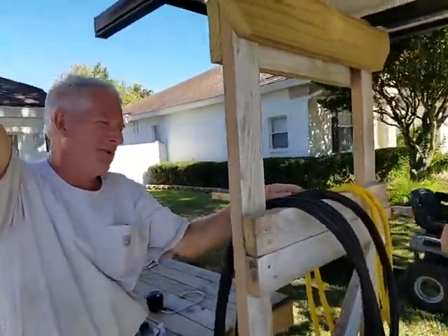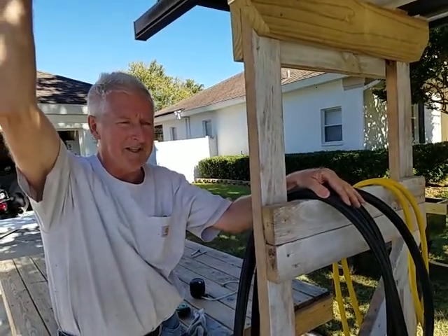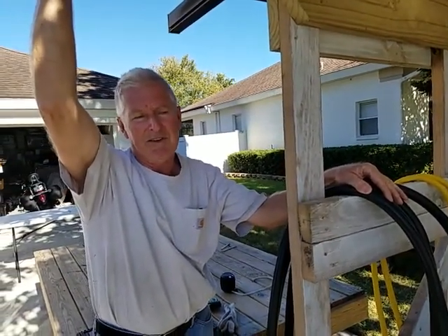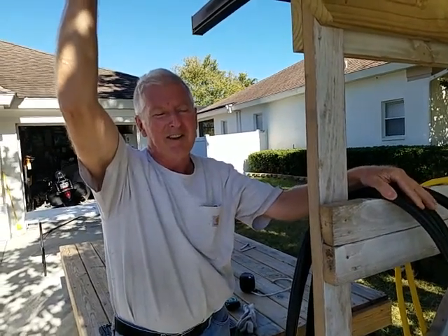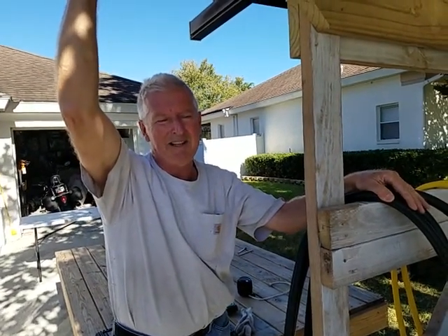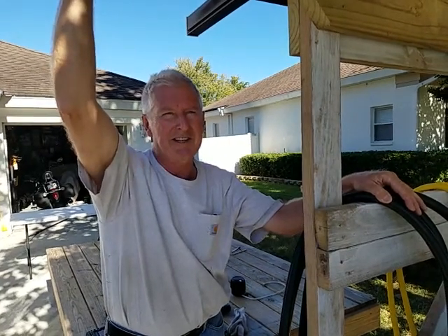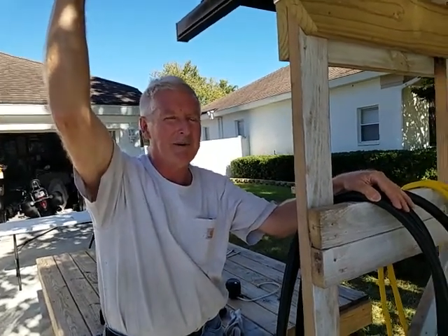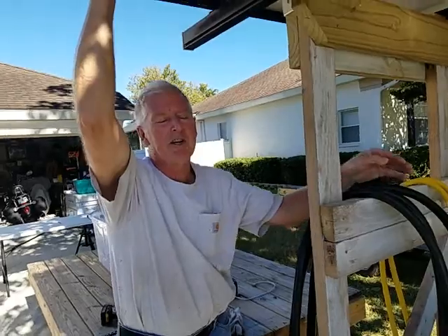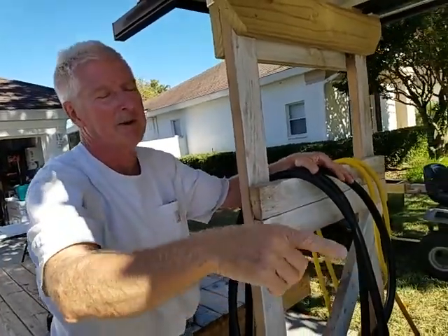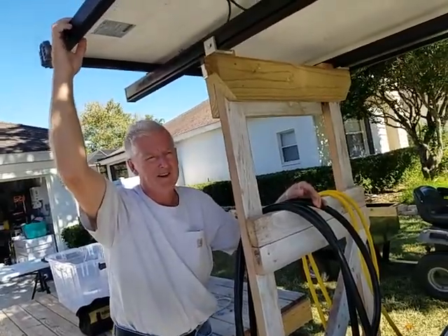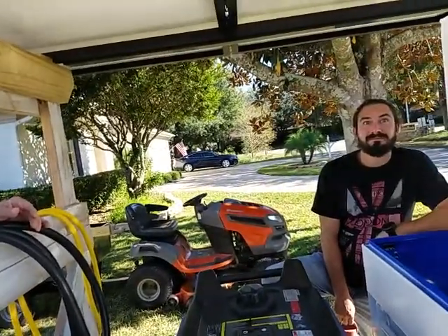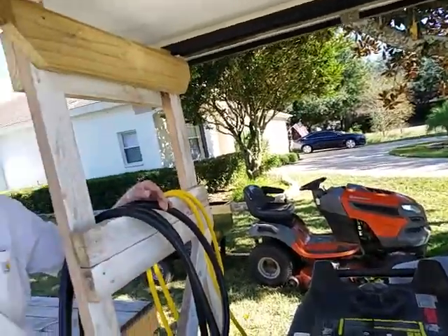Because right now I picked 25 feet to get in our budget. Yeah. But you can't really go over 50 feet because a 50 amp cable, this is number 6 wire, you're going to exceed the capacity of the wire to carry the electricity. So it looks like we need to put another receptacle somewhere. Maybe. Because they just all connected together. You could literally plug this into the receptacle that you plugged into today if you can get this in the sun somewhere. Which we probably won't be able to. We're 100 feet away to get to the sun from now.